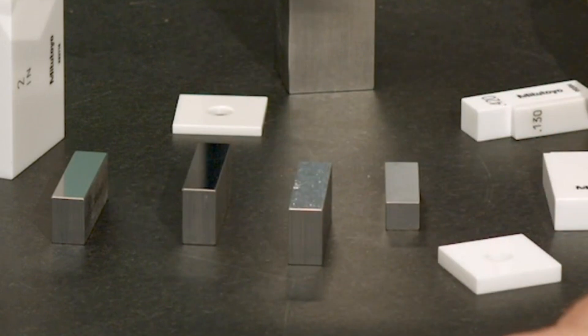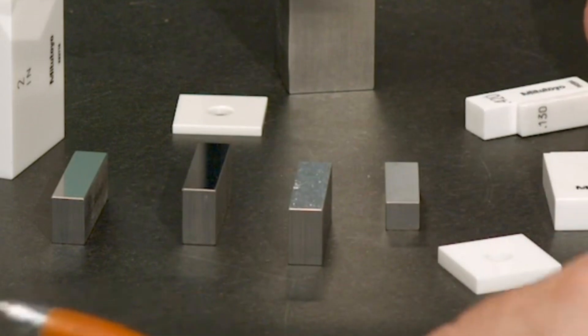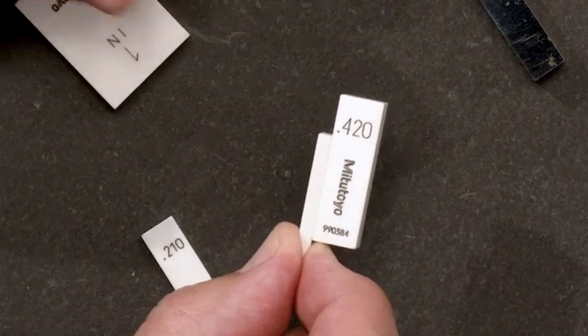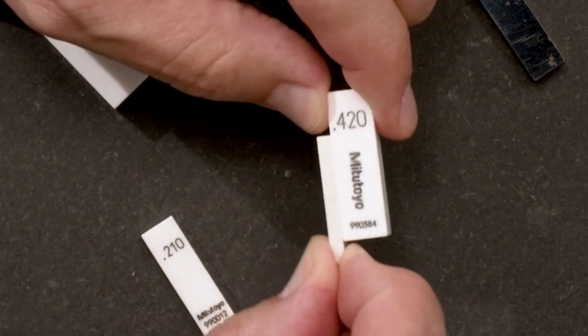That's a brief introduction to Gauge Blocks. How do we use them? Gauge Block faces are very flat and very smooth. The reason for this is that that allows Gauge Blocks to ring together. Without using any adhesive, Gauge Blocks can be brought together and the flat, smooth surfaces will adhere to each other without causing any damage.